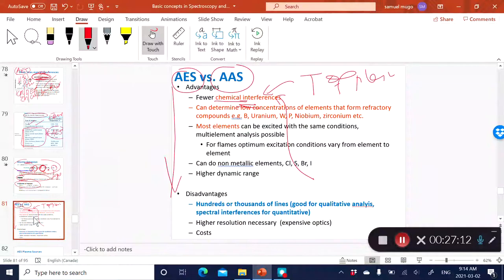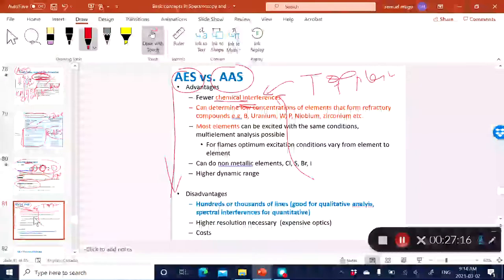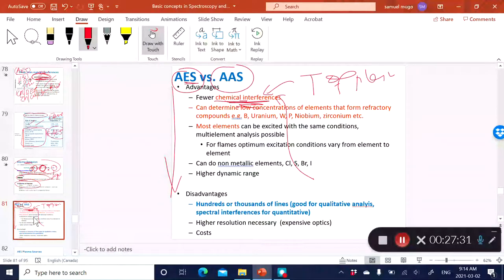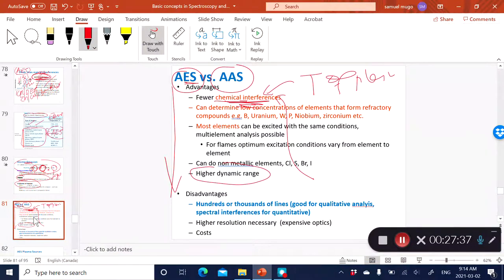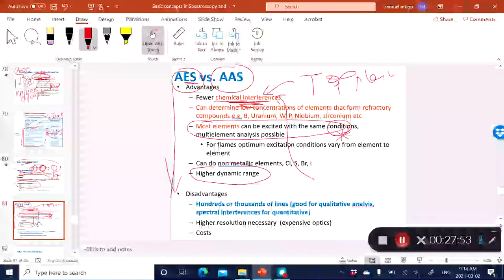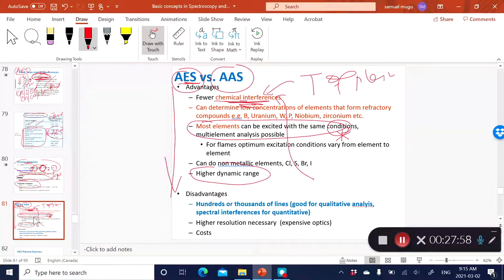Further advantages of ICP-OES over AAS include a very high dynamic range and the ability to analyze multiple elements simultaneously. AAS can only analyze one single element at a time, whereas with ICP-OES you can analyze almost everything in the periodic table at the same time. One disadvantage is cost: ICP-OES (ICP-AES) is about 100K, whereas a flame AA is around 30K.